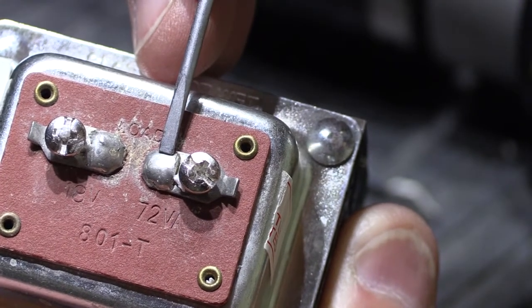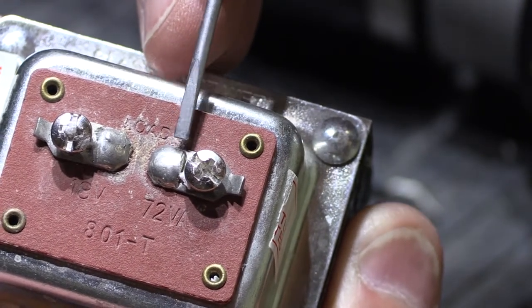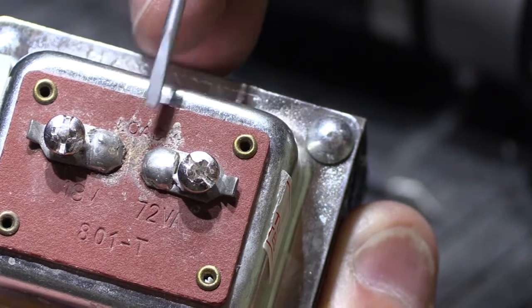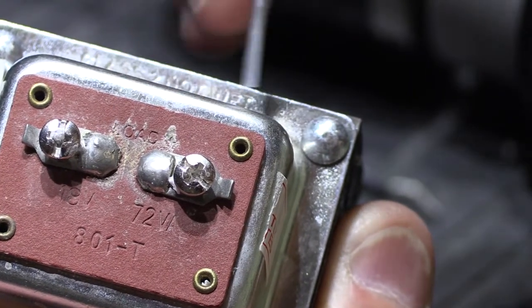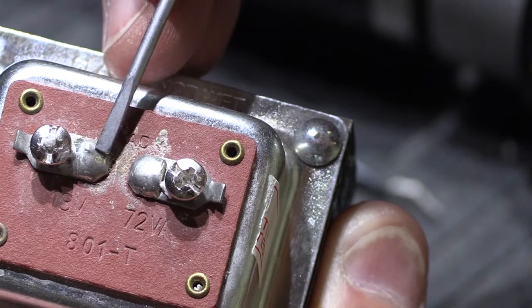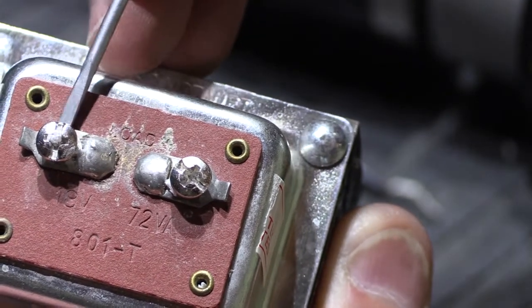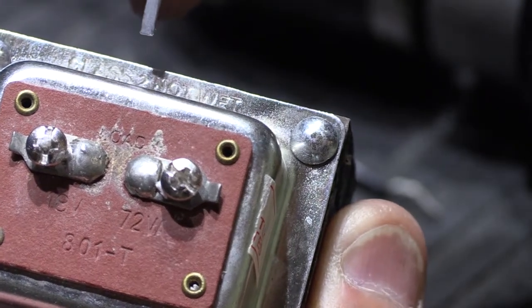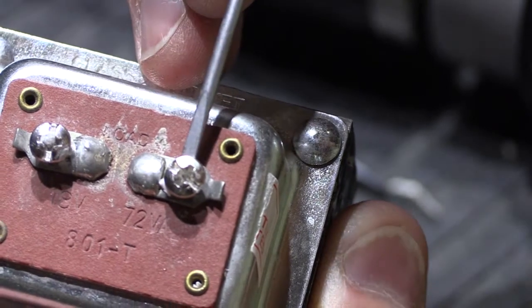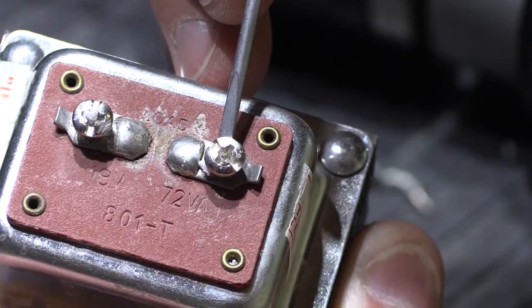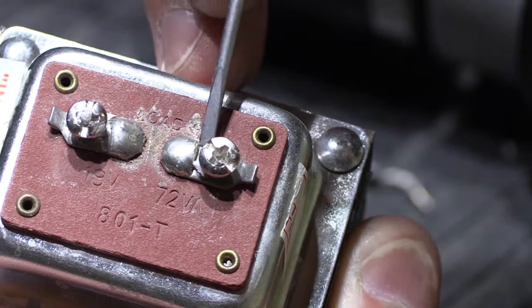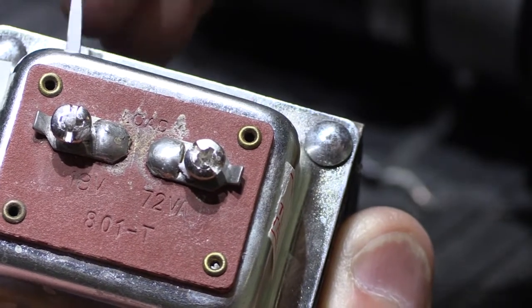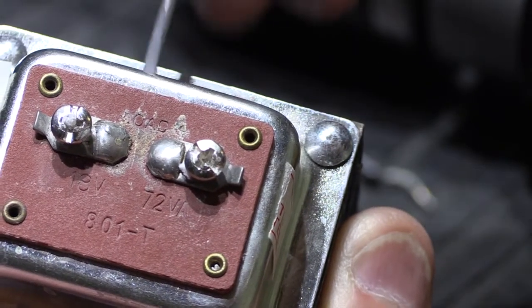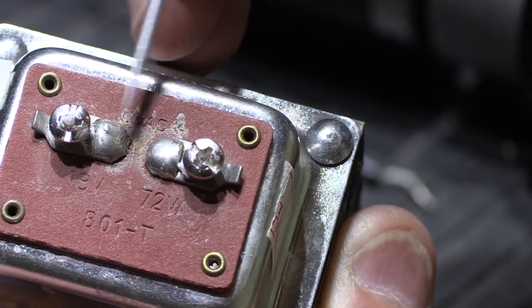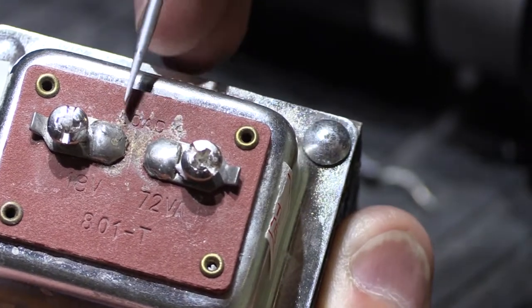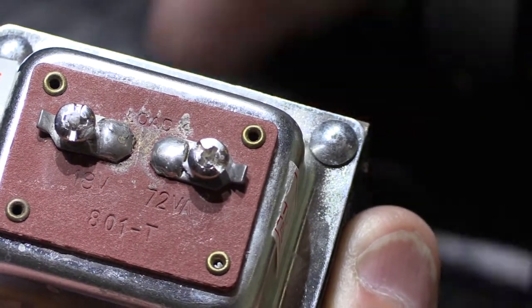The blobby things are solder. Underneath the solder there's a hole in each metal tab, with a wire coming from inside the transformer through the hole, soldered in place — that's how the voltage gets out of the secondary windings into the screw terminals. So the very first thing we have to do is desolder this, because when we take the transformer apart, we have to remove this end cap, and to get it off, you have to desolder these so the wires aren't holding it in place.